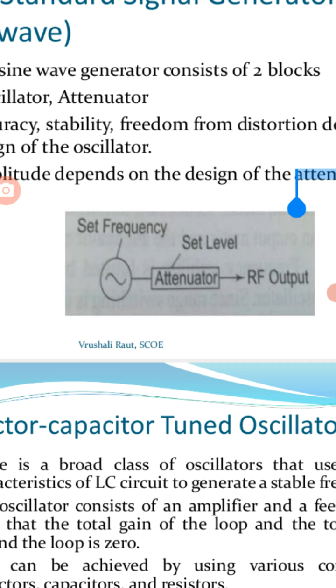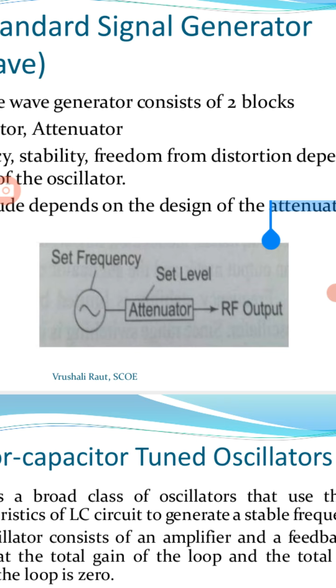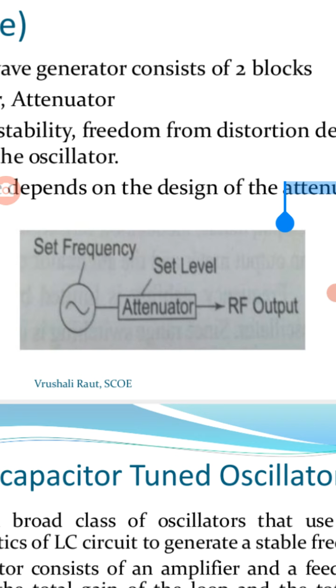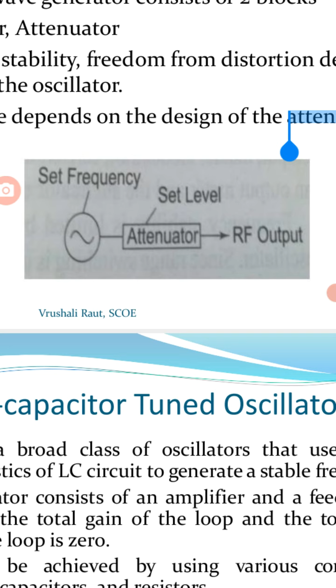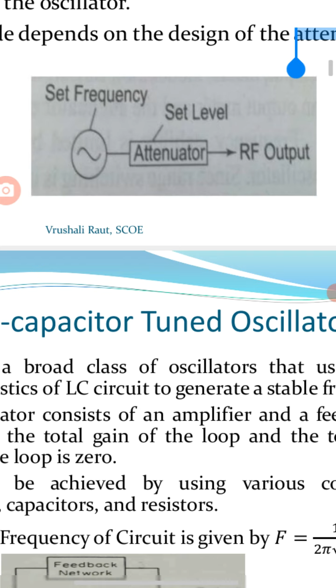Standard signal generators are sine wave generators. In the figure you will find that the set frequency is the oscillator frequency. Then the attenuator will attenuate the signal to the expected level. That is what the RF output is. So level setting and attenuator will bring your signal within your expected limit.